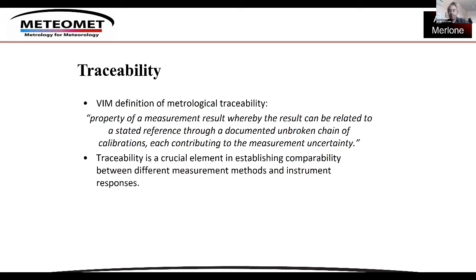Now, allow me to touch on the concept of traceability, which is a property of a measurement that is related to the standards, to the reference, through an unbroken chain of calibration. If you want a measurement to be traceable, you need to calibrate the instrument so that each calibration gives you an idea of the uncertainty. Traceability is needed so that we are speaking the same language, so that if we have calibrated in the same way, we are sure our instrument results can be compared.